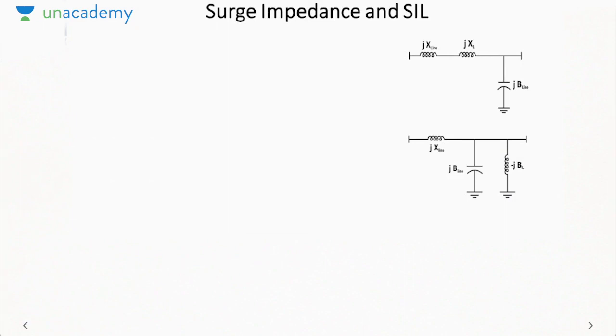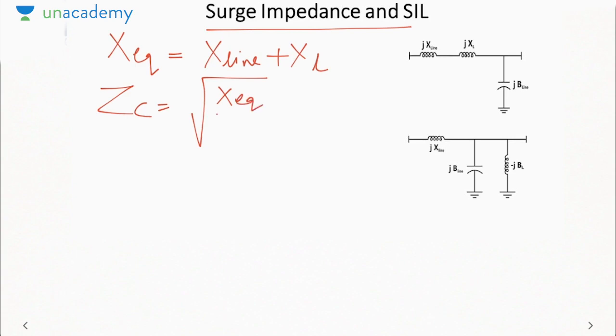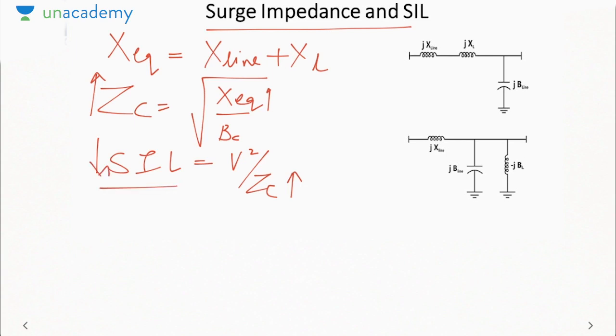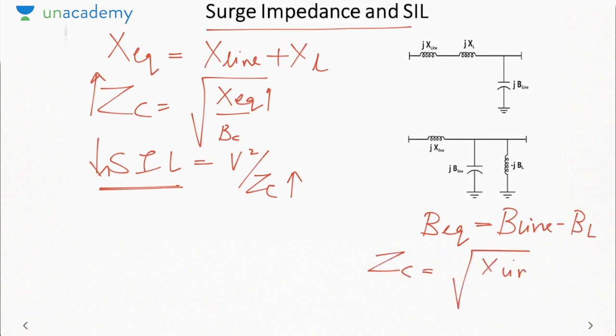Now what about the reactor? In case of series reactor, X equivalent will be X line plus XL. So ZC will be under root X equivalent by BC. Since X equivalent increases, ZC increases. So SIL, which is V square by ZC, as ZC increases, SIL reduces. What about shunt inductor? Here B equivalent will be B line minus BL. So ZC will be under root X line by B equivalent. Since B equivalent reduces, ZC increases and SIL reduces as ZC increases.